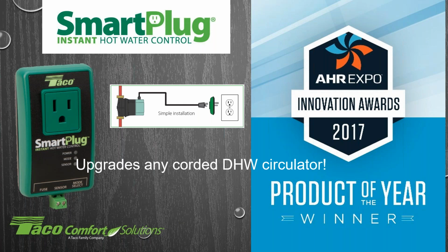It's going to change things for you. So what this does is that it learns events. It's not looking for actual temperature. It's looking for an event. And an event in water usage is a temperature rise in the pipe itself, or duration at that temperature, and then a temperature fall. And it records that as an event and says, okay, 5 o'clock on Sunday, hot water was used.